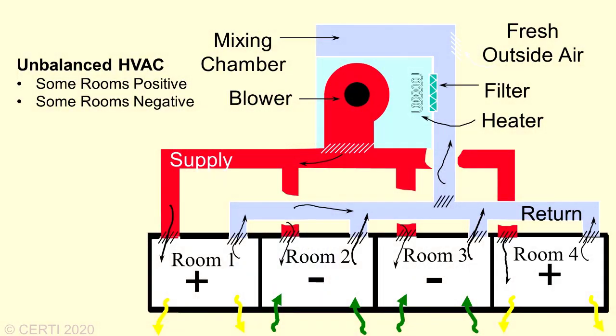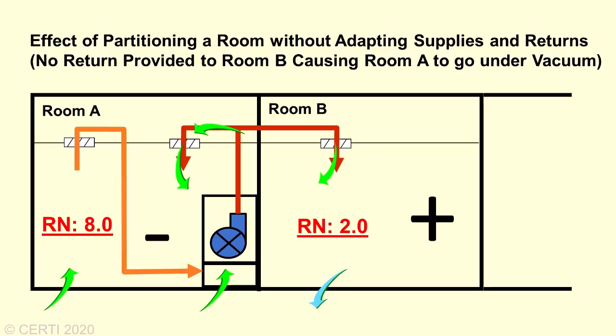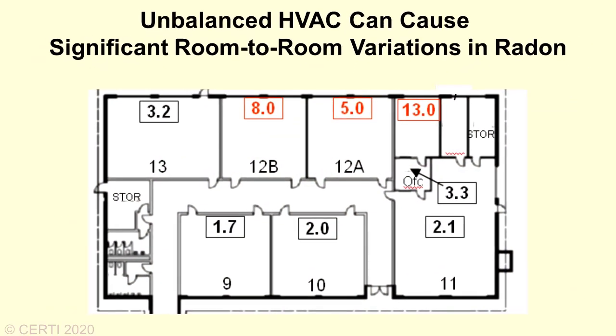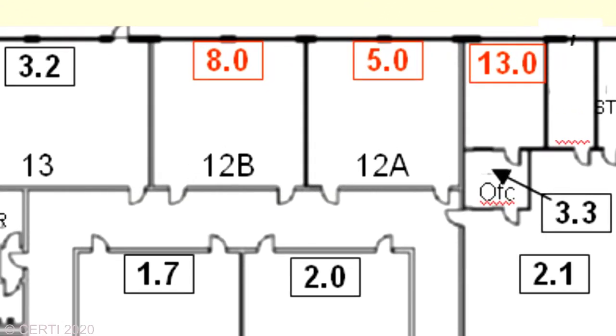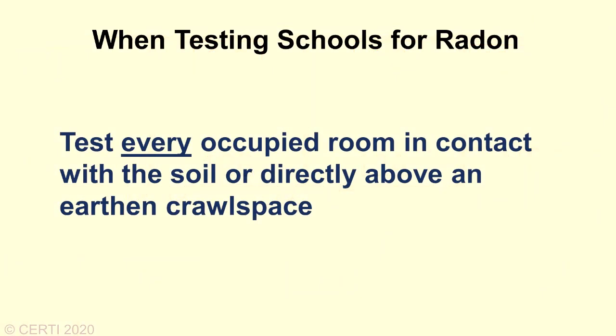The effect of closing a supply grill is to make that particular room go under negative pressure, since air is still being taken out of the room with less air being supplied. This negative pressure condition can cause radon to enter that particular room, but not adjacent rooms where the supply has not been restricted. Another example of unbalancing is when remodeling occurs and a partition wall is installed in an existing classroom, or perhaps a movable room partition is used. If both supply and return air is not provided on both sides of the separation, the side with the return air can go under negative pressure and cause high radon levels on that side. The effect of unbalanced airflow is why one often sees significant room-to-room variations in radon levels. It is the reason why in a school or office building it is important to test every occupied room in contact with the soil or directly above a crawl space.